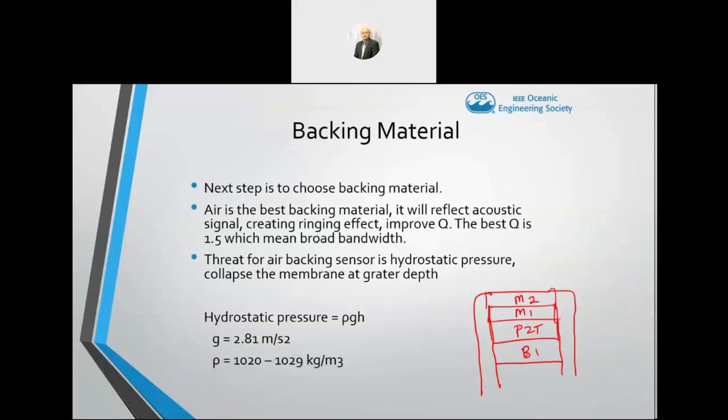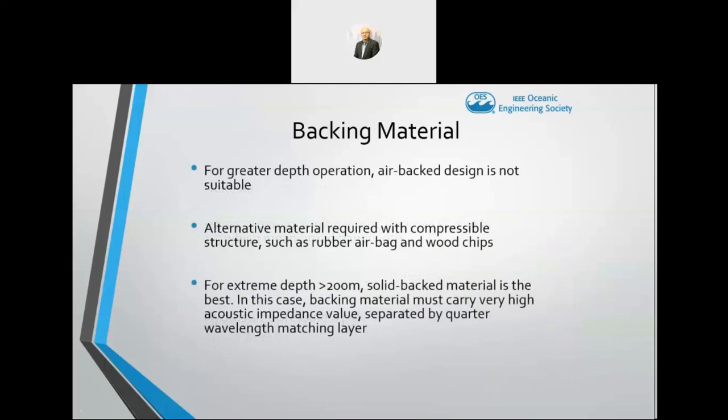So normally we might need a backing layer so that the generated sound to the back will either be absorbed or reflected to the front. So all the generated sound will go in a specific direction and not all directions. The process is also the same. We can have an air backing, we can also have a liquid backing layer. So it depends on what type of application.